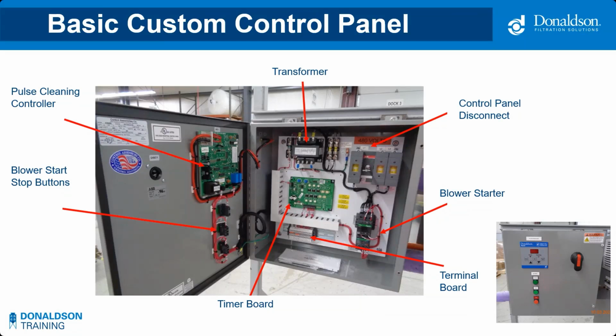Below the disconnect is a contactor and an overload, which is the main blower fan starter. In the field, the output of the starter would be connected to the main blower fan motor to provide 480 volts in this example. The rest of the panel does not need 480 volts. So we have a transformer to the left of the disconnect switch, which will transform the AC voltage from 480 volts AC on the primary side down to 120 volts AC on the secondary side. Other control panels may also include a power supply, which will convert the AC voltage to a DC voltage. So transformers are AC in and AC out. Power supplies are AC in and DC out.